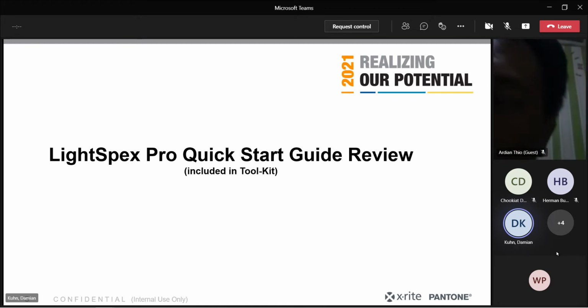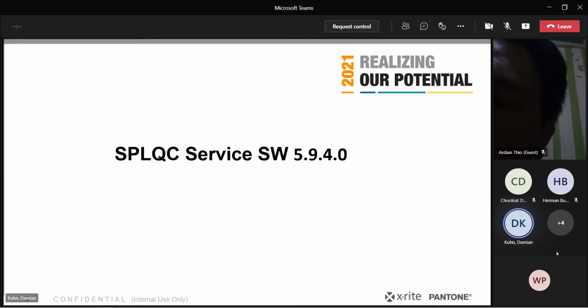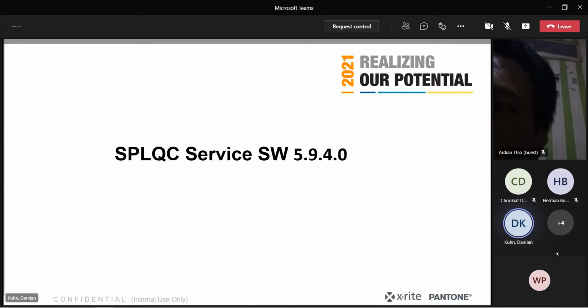And now I would like to move on with the SPL-QC service software that you will get access to. I believe all of you are actually using the SPL-QC service software. However, there is now a new version, and that new version, of course, supports the Lightspex Pro instrument. But that was not the only change we made. As we worked on the software, we made additional changes, and I would like to outline them in a couple of PowerPoint slides before we look at the changes directly, mostly in the service software. And once we have covered the SPLQC service software, we would then move to the second service software, the LightView 2 software you will get as part of the toolkit. And I will introduce that software in the next 45 minutes.